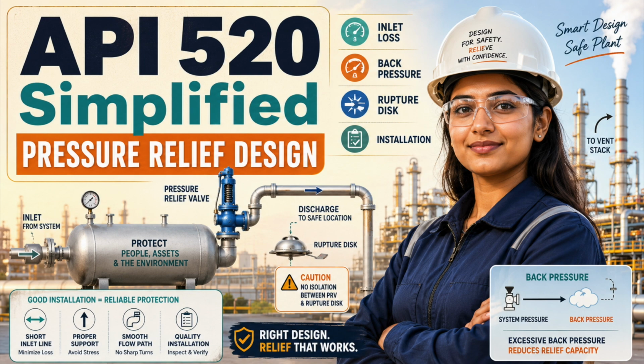That distinction changes everything. The first question is not, what valve size do I need? The first question is, what can actually cause this equipment to overpressure? A blocked outlet, control valve failure, utility loss, exchanger tube rupture, external fire, thermal expansion, gas blowby, compressor failure, loss of cooling, uncontrolled reaction, or steam breakthrough can each create a different relieving load, temperature, pressure, fluid phase, and duration. If the scenario is wrong, the calculation is wrong. It does not matter how accurate the equation looks or how polished the datasheet appears.